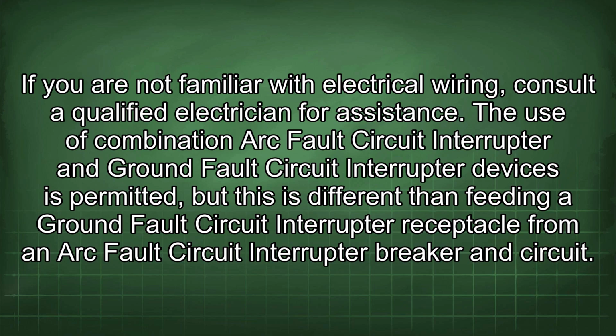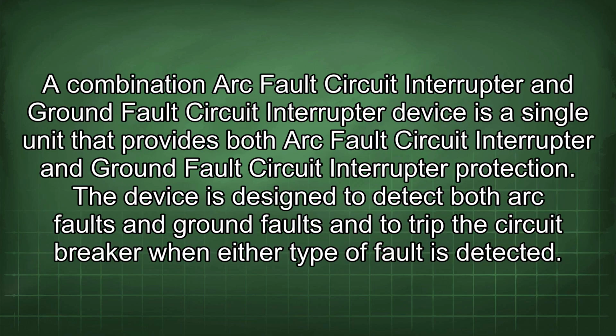The use of combination arc fault circuit interrupter and ground fault circuit interrupter devices is permitted, but this is different than feeding a ground fault circuit interrupter receptacle from an arc fault circuit interrupter breaker and circuit. A combination arc fault circuit interrupter and ground fault circuit interrupter device is a single unit that provides both arc fault and ground fault protection. The device is designed to detect both arc faults and ground faults and to trip the circuit breaker when either type of fault is detected.